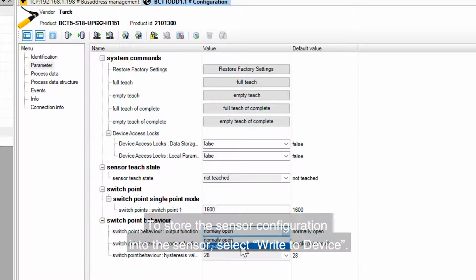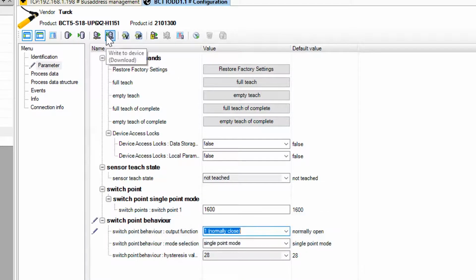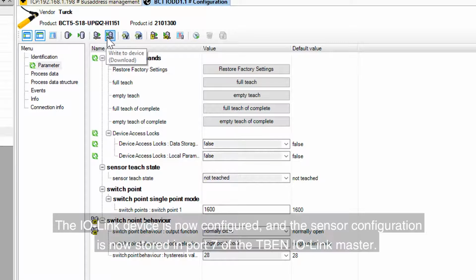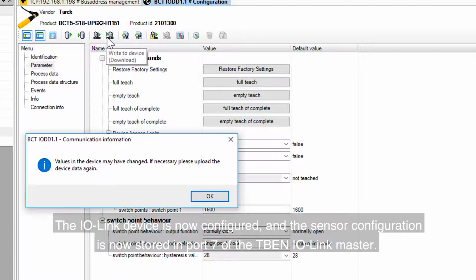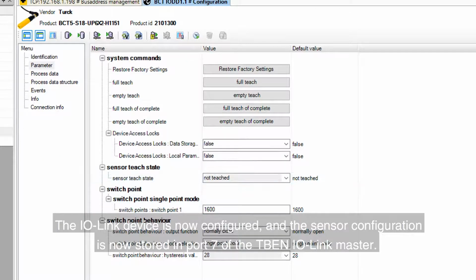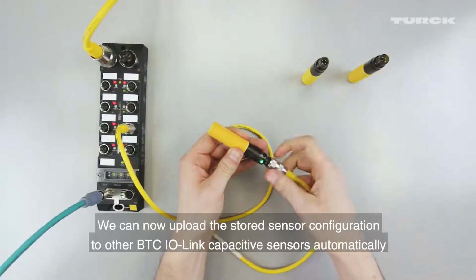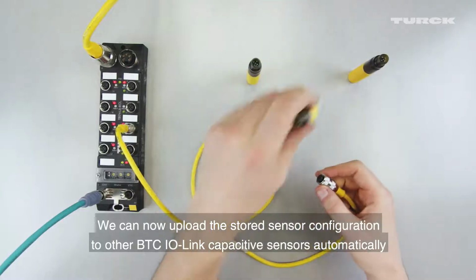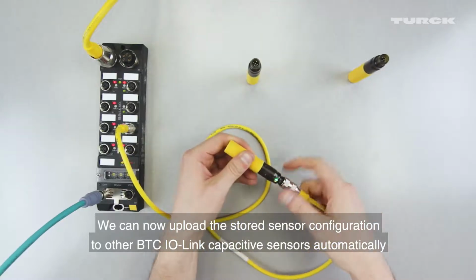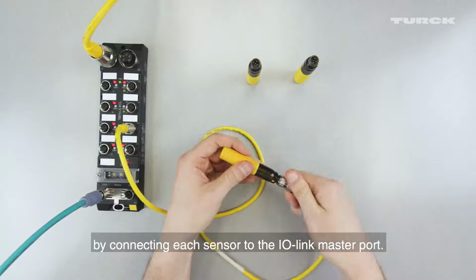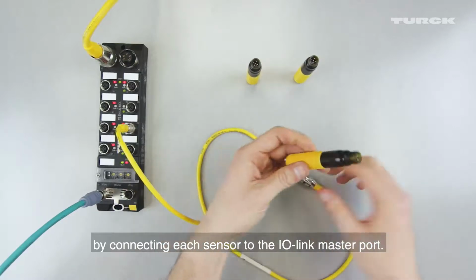To store the sensor configuration into the sensor, select Write to Device. The IO-Link device is now configured, and the sensor configuration is now stored in port 7 on the TBEN IO-Link master. We can now upload the stored sensor configuration to other BCT IO-Link capacitive sensors automatically by connecting each sensor to the IO-Link master port.